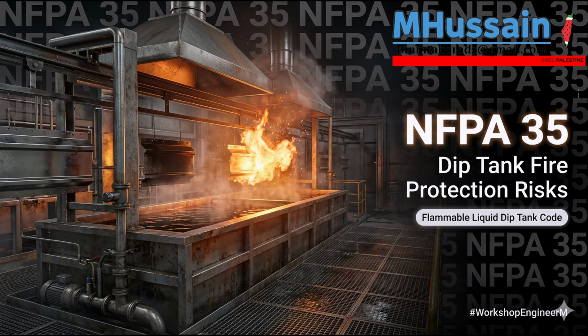Can't we just filter and recirculate the air? The energy cost is undeniably one of the most painful operational expenses for these facilities. Owners constantly want to recirculate to save on heating and cooling. Naturally. But standard recirculation is a death sentence in this environment because you are just taking explosive vapors and pumping them back into the room. Oh, right. However, the standard does offer a highly engineered compromise. Recirculation of exhaust air is permitted, but only if you install a continuous, fail-safe vapor monitoring system.